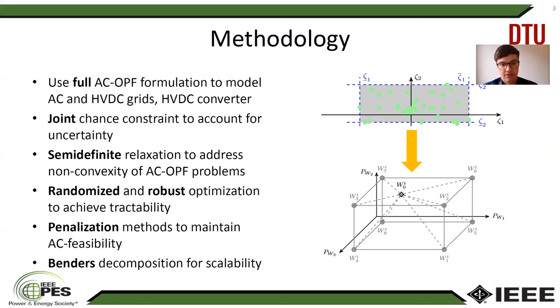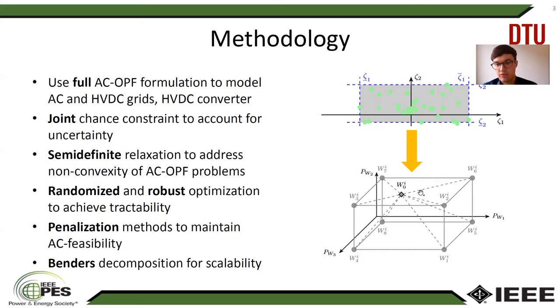The chance constraints are in their standard form intractable, so we propose a procedure using randomized and robust optimization to achieve tractability, illustrated in the two figures on the right. In the top figure, we draw a certain number of scenarios of wind forecast error realizations — shown in green — and construct an uncertainty set enclosing all these scenarios. In the bottom figure, we enforce the system state for the forecasted state (denoted with subscript zero) and all vertices of the uncertainty set, with the system state inside described as a piecewise affine approximation between the forecasted state and the corresponding state at the vertices.